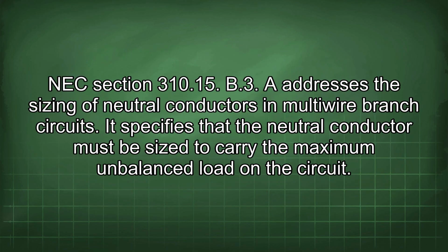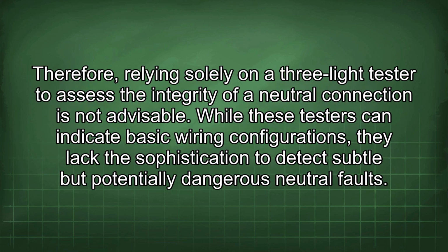NEC Section 310.15(B)(3) addresses the sizing of neutral conductors in multi-wire branch circuits. It specifies that the neutral conductor must be sized to carry the maximum unbalanced load in the circuit. Therefore, relying solely on a 3-light tester to assess the integrity of a neutral connection is not advisable. While these testers can indicate basic wiring configurations, they lack the sophistication to detect subtle but potentially dangerous neutral faults.